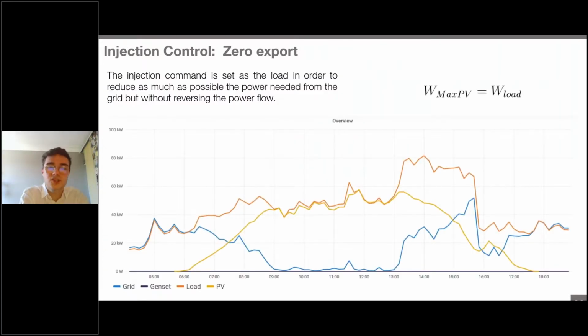Here are some interesting screenshots showing how the system behaves once the power controller is installed. In orange you have the load, in blue the grid, and in yellow the PV production. You can see that around 9 o'clock the PV production equals the load and could potentially exceed it, so at that moment the e-power control curtailed the PV production to ensure it never exceeds the load demand.